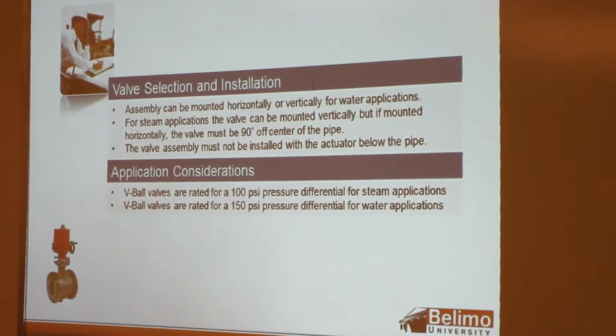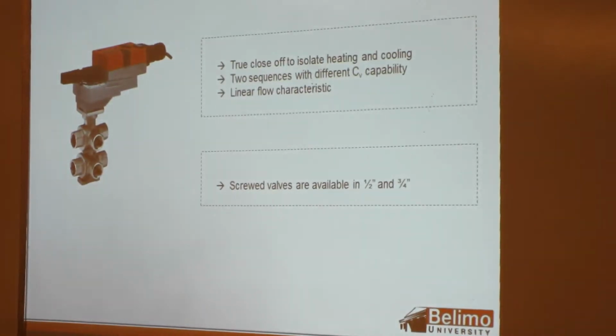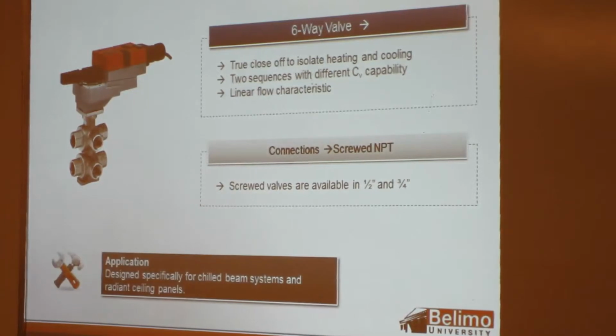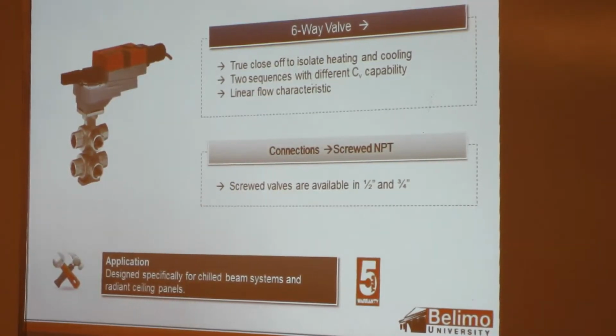So the V-ball valves are rated for 100 psi pressure differential for steam, 150 differential for water. The 6-way valve. With the 6-way valve, we have true close-off in the middle range of rotation. We can have 2 different CV capabilities. And as most of you probably know, typically a heating application is going to be a lower CV than a cooling application. That's why we have it set up this way. They do have a linear flow characteristic. They're available in 1/2 and 3/4 inch. I think the top CV is like 2.9 CV or something like that. So they're meant for smaller applications, as you can tell, 1/2 and 3/4 inch. Designed specifically for chilled beam and radiant ceiling panels.